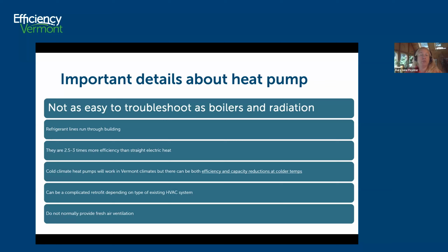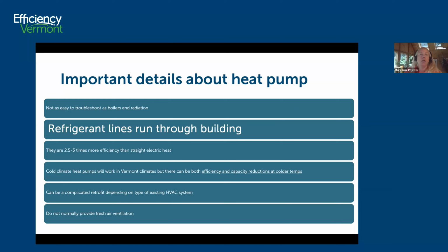And oftentimes you have to bring in a contractor when there is an issue, because you won't be able to figure it out because it has something to do with the refrigerant. Maybe you've got refrigerant leaks. Maybe you've got a failed fan somewhere or a failed compressor. So with heat pumps, you will have refrigerant lines running through the building. You might have a mini split. It's not that much of it isn't running through the building, so it's just coming up your outside wall. But if you have a variable refrigerant flow, a VRF system, those refrigerant lines are going to be running all throughout your building.